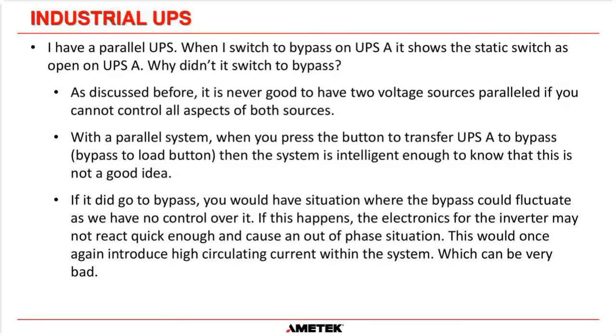As we've discussed before, it's never good to have two voltage sources parallel together if you cannot control both sources. When you have two inverters connected in parallel, there's electronics that speak to each other, and we can control those two sources, and they are always perfectly in sync. But when you press one of the UPSs to transfer to bypass, if we allowed it to do that, then you would have one system on bypass, one system on inverter, and if the bypass, which we have no control over, changes or goes out of tolerance, then you are going to have circulating current again, pretty much identical to that situation that we had before.